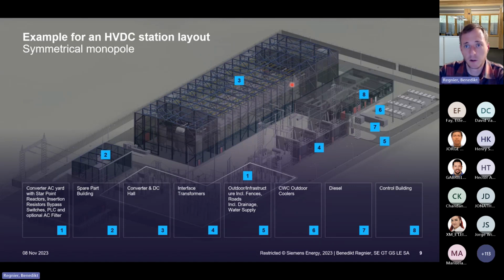And number 6, as we are talking here about IGBTs, they produce heat, and we need to make sure that the IGBTs and the whole power modules are sufficiently cooled always. That's why we have our outdoor cooler banks as an important part. Diesel generator. Normally, our station is self-supplied via the interface transformer. We use the tertiary winding to supply our station auxiliaries, but for example for startup, or especially during the black start, where a local DSO grid is also not available, we need to use diesel generators to support the startup of the system until the station is operational and we can support ourselves again from the tertiary winding.